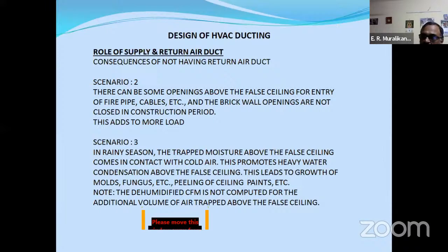So these are very, very common things. The builders don't put the wall above the false ceiling for the washroom. Say what is there about that? It has significance. When you are planning a building without a return duct, with the false ceiling expected to work as a return duct, please take care that you build the wall wherever required and close all the openings, like cable entries, fire pipes, plumbing pipes or anything like that. Otherwise, all the air above the false ceiling will find n number of spaces to raise the temperature and humidity in the conditioned space.